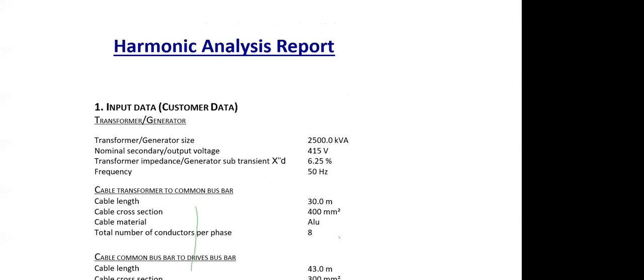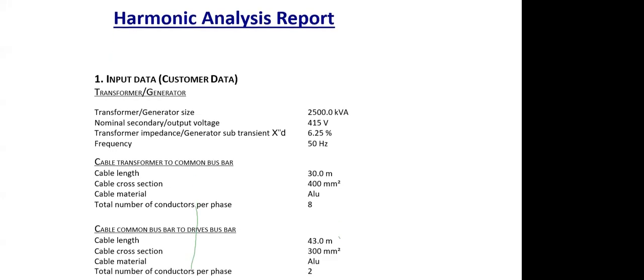Here is a study where I have a system in which my transformer size is 2500 kVA, that is 2.5 MVA, and it's a 415 volt low voltage system. Transformer impedance or generator subtransient is 6.25%. In my last discussion I discussed how this transformer impedance is very important. What is the cable length? 30 meters. Cross section is this. Cable material is this. These are basically the main MCC panel or transformer-associated substation data.